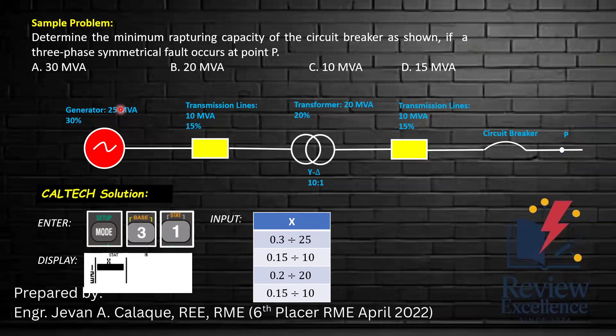Next, for our primary transmission line, we have 15% or 0.15 divided by 10 MVA. Then for our transformer, we have 20% or 0.2 divided by 20 MVA. For our secondary transmission line, we have 15% or 0.15 divided by 10 MVA. So input lang natin to sa ating calculator, engineers.